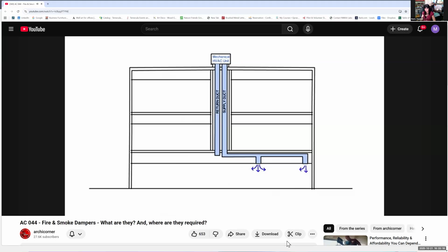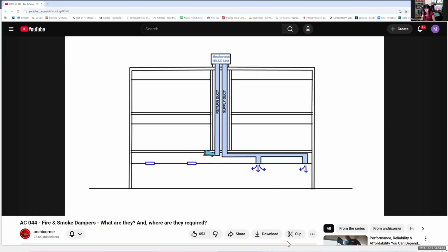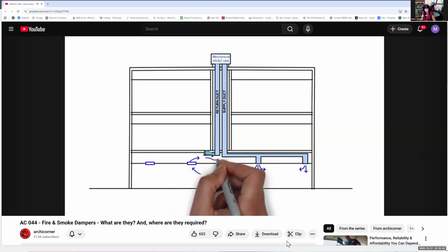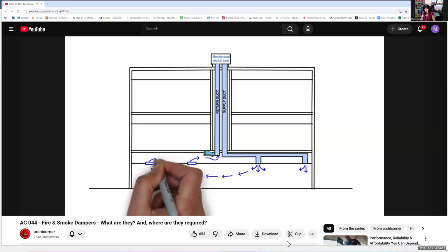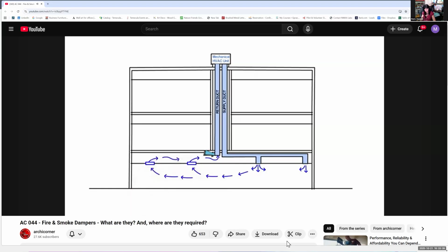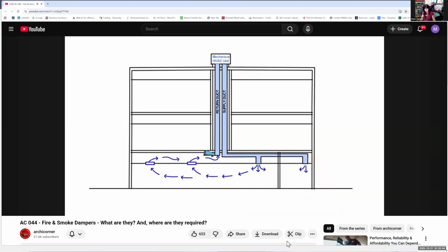As for the air that will return to the unit, the duct may terminate here, and the suspended ceiling may have return air grills that do not have ducts above. Due to the pressure that is created by the air that is being supplied to the space, the air will find itself a way back through the return air grills, through this return air plenum, and back to the return duct. And just bear with me, but let's assume that there is a fire-rated wall at this location.